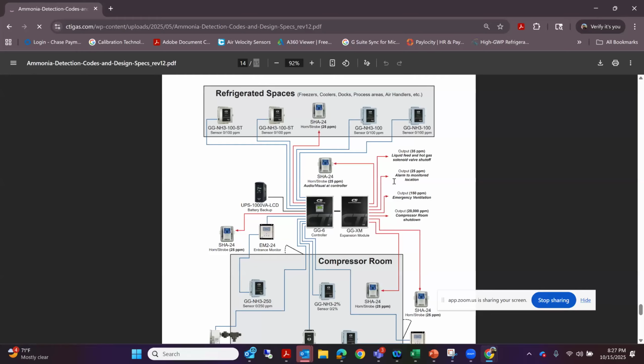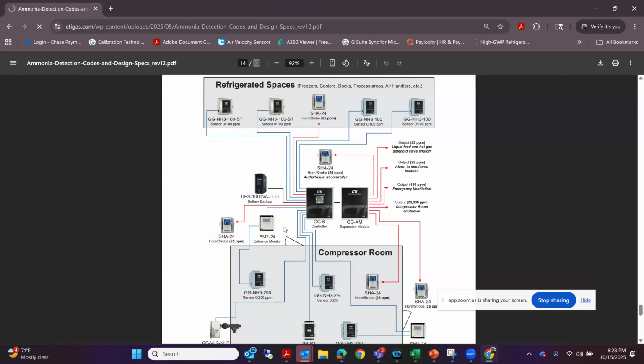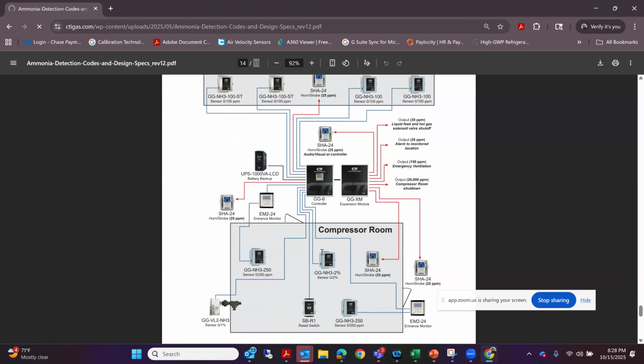That's one of the things that makes it nice, that's where CTI would try to power the sensors with the 24 volts, along with slamming relays in here to trip on that audio visual at the same time, because now you're pulling that same 24 volts all through the same conduit, which saves a little bit on labor. Same thing with stack lights going around the compressor room as well. Being able to pull and daisy chain stack lights in and around the compressor room for determining levels of concentration.